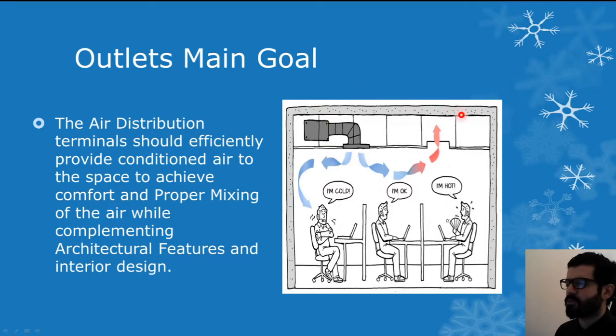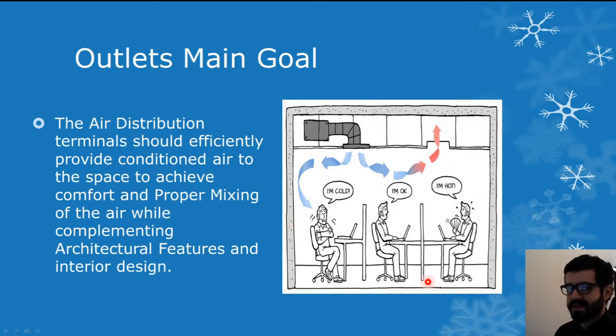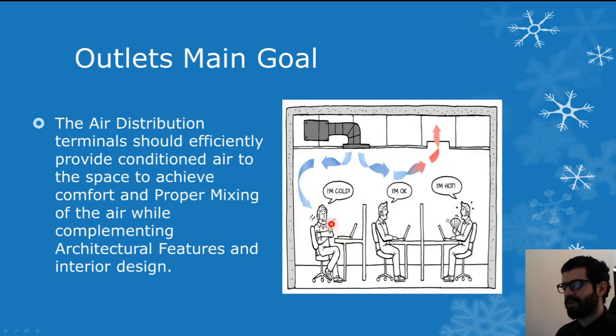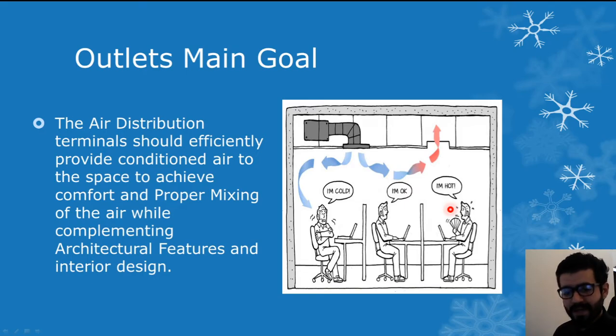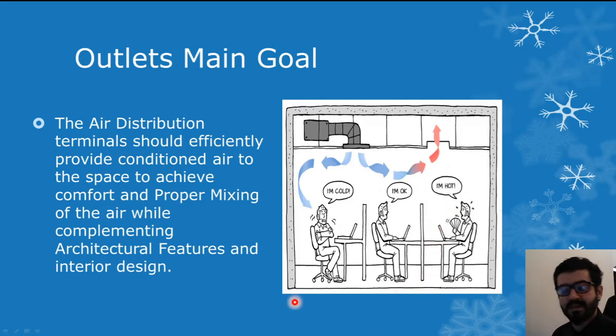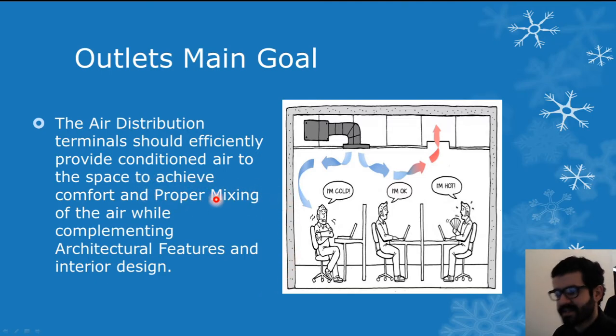Let's take a look at this visual representation on the right side. This represents a poorly designed distribution system, where you have an outlet, and in one cubicle within an office, one employee is feeling really cold, one is okay, and the other is feeling too hot. This clearly represents an uneven distribution of air within the space, therefore the design is considered a failure — because you are not able to meet the required criteria, which is proper mixing in this case.